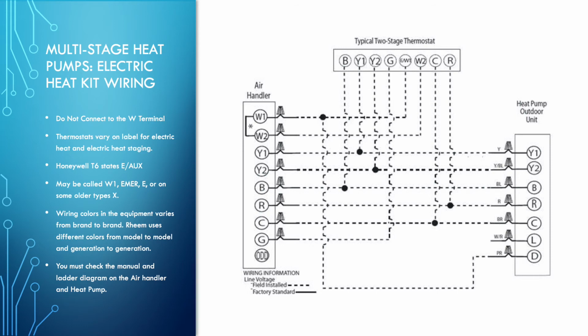the actual unit. Now, the electric heat kits are powered up by timed sequencers. If it's a 10 kW, it is likely only to have one stage of electric heat. And that's usually one sequencer that's got two stacks on it that are energized on a timing delay. 20 kW heat kits will usually have two sequencers set up. And it'll also typically have two separate wires to energize those individual sequencers. And so you got to pay attention to that.